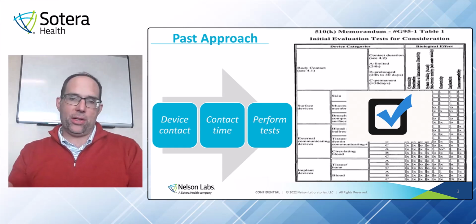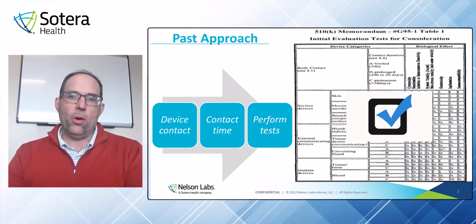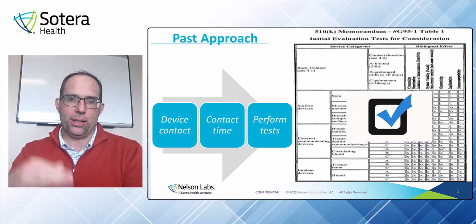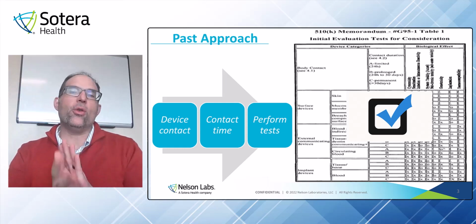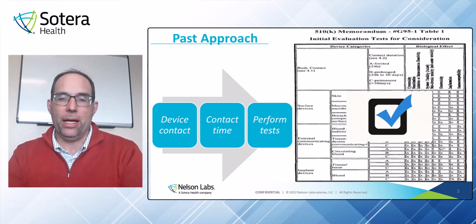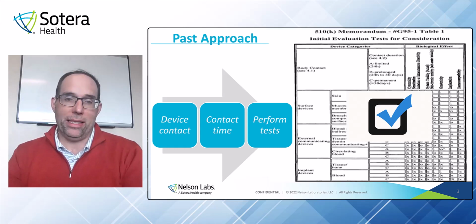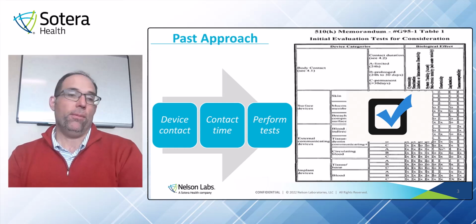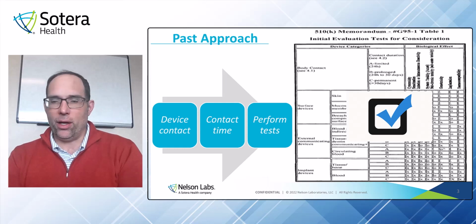It was really easy, actually, and we didn't need a whole lot of biocompatibility experts because anybody who would ever learn how to follow a chart could do biocomp. It was just sometimes you had to have a misinterpretation or agreement or disagreement on how the device contacted the body or the duration. But once you agreed on that, everybody knew what test to do. So this was what we called a checkbox mentality. So you just basically did the tests regardless of any other considerations.